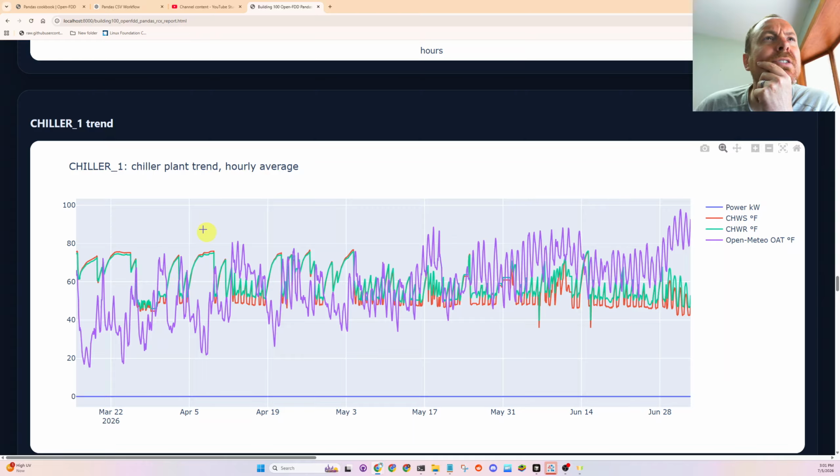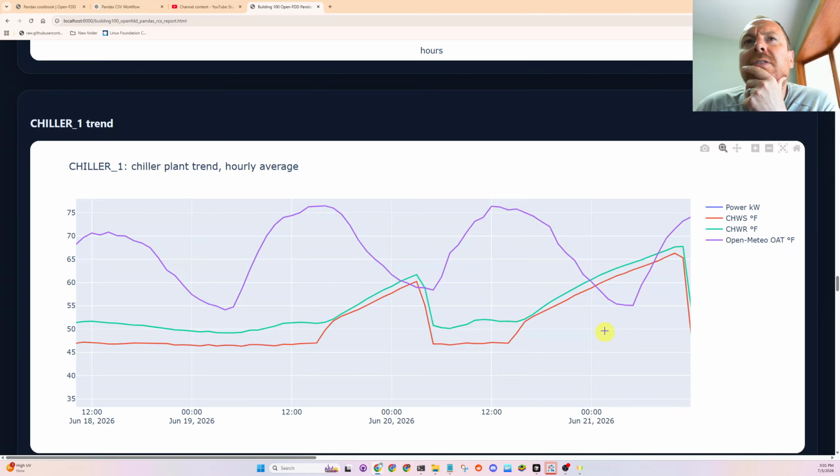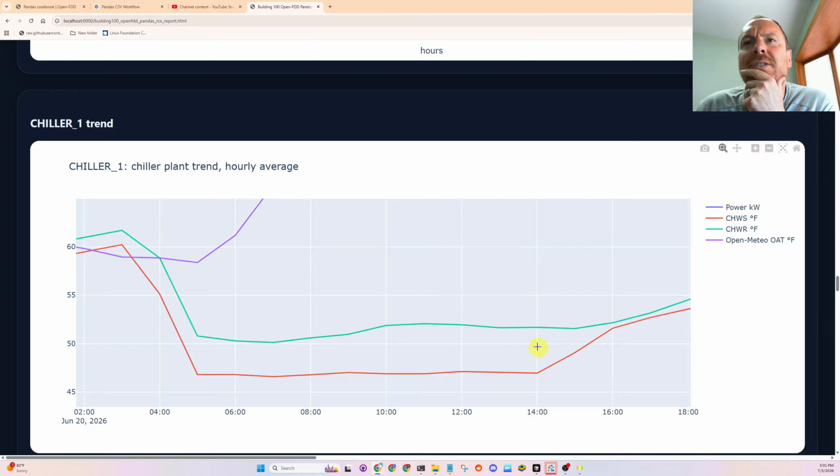And okay, chiller plant trend. We have a chiller plant power. Looks like the power meter does not work. And we could even do, this is the chilled water system when it runs. When it runs, the return temp back to the chiller is like 51 and 46. So 46-degree water is not that cold. Sometimes it's even colder. 6-degree delta.